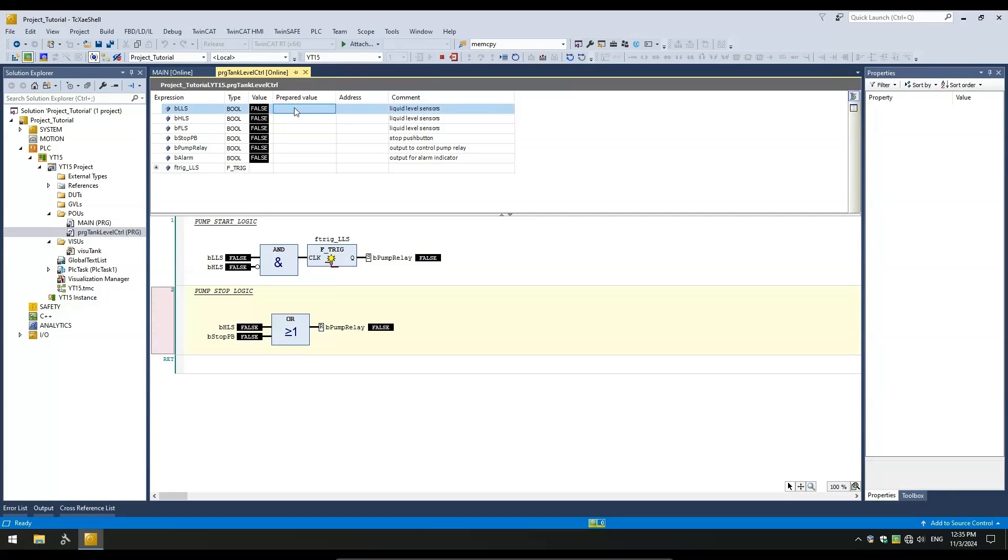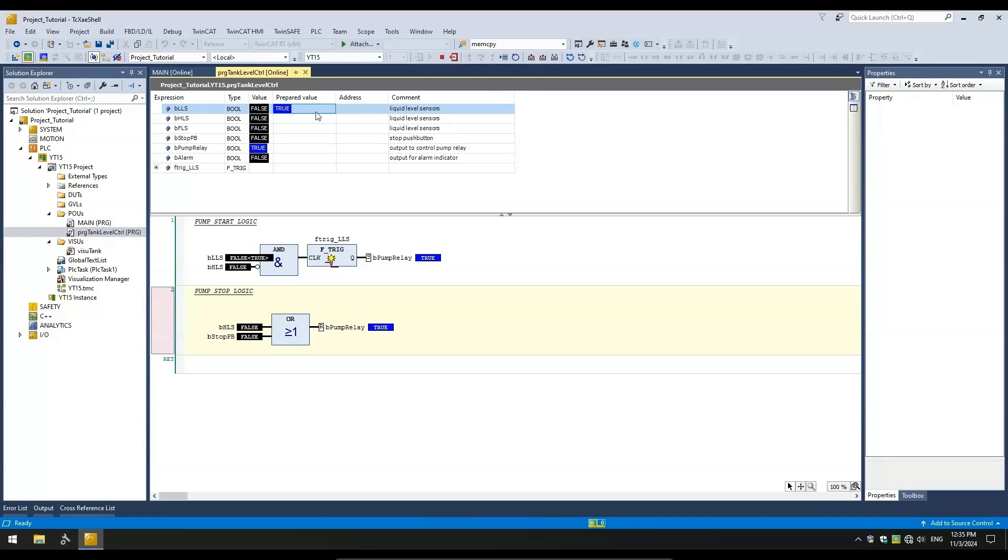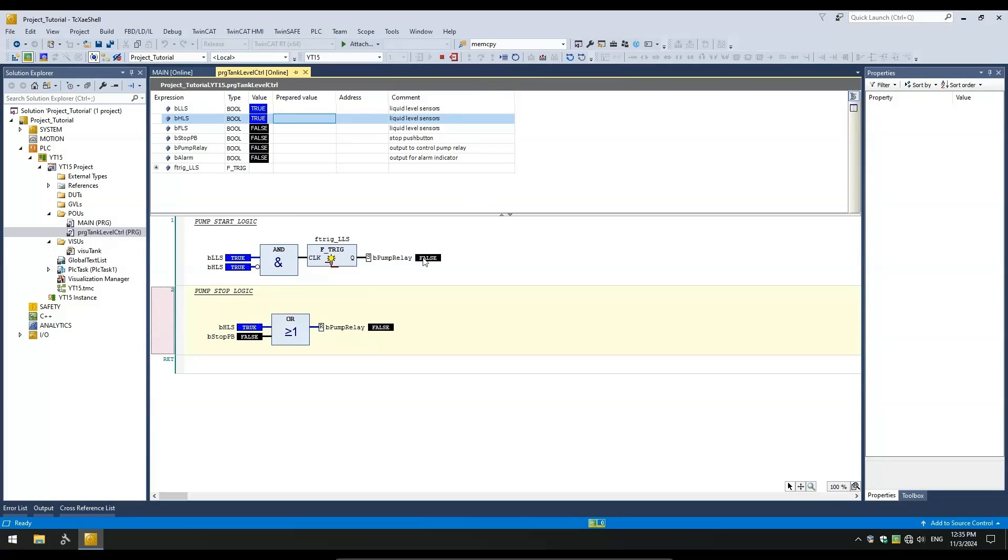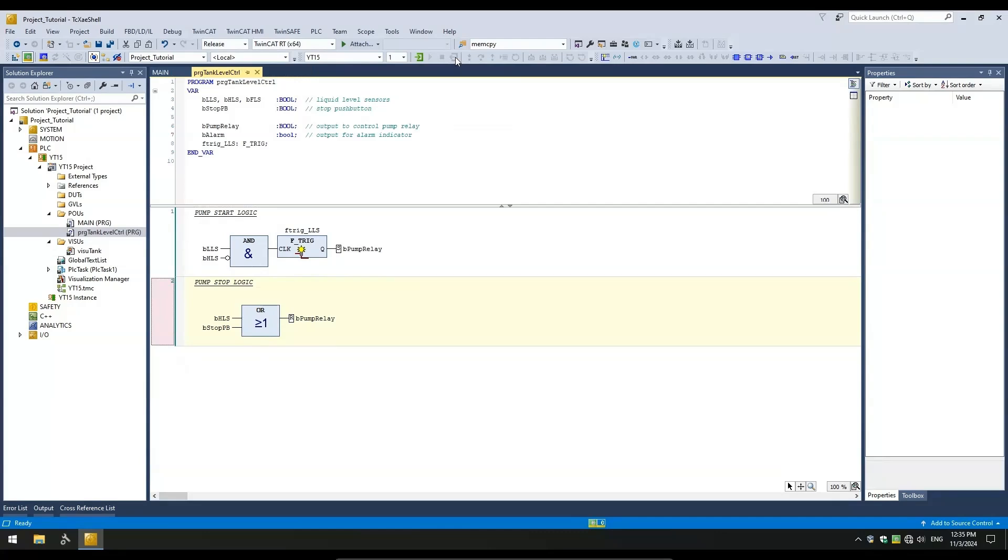Now we can log in and test our PLC program. A falling edge on the LLS should start the pump and when the HLS turns on, the pump should stop. So, first I will assert the LLS and then turn it off, which should turn on the pump. As the tank fills, LLS turns back on and then HLS will turn on and the pump should stop. Our basic start and stop logic is working as programmed.